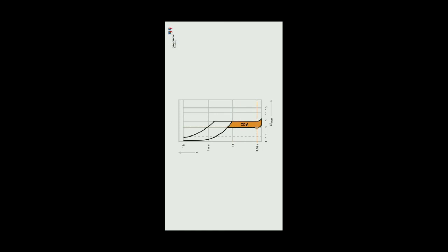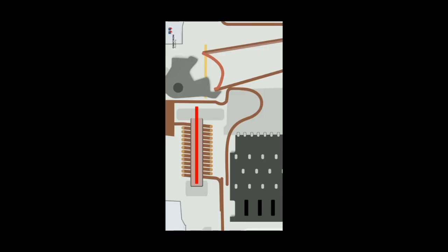An MCB must open a circuit instantaneously when it encounters a short circuit at several times the nominal current. A solenoid and a piston are the elements used for instantaneous tripping. A short circuit creates an instant magnetic field that moves the piston and operates the breaker. Interrupting high fault currents can result in heavy arcing.